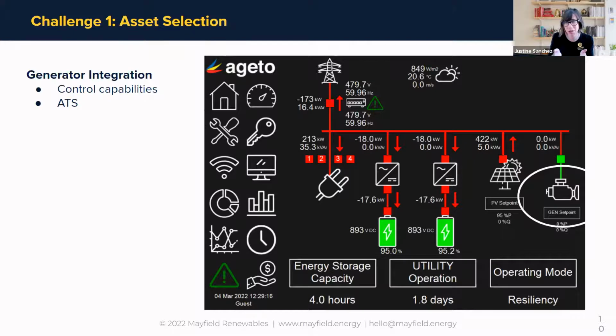Okay, but what if we want to run the generator on its own for some reason? Would you be able to? Yeah, most of those generators that have base load capabilities can also operate in grid forming or isoch mode. Many of our systems are set up and programmed so that if the battery system has a fault or can't turn on for some reason, or the solar isn't working, we'll default the generator back to isoch or grid forming mode to power up the facility. So we always have multiple layers of automated redundancy in our system. That's great.